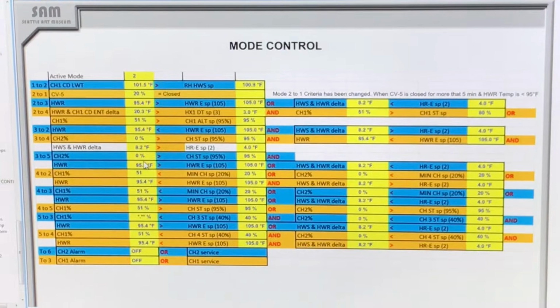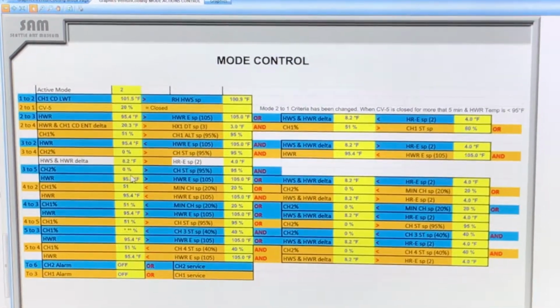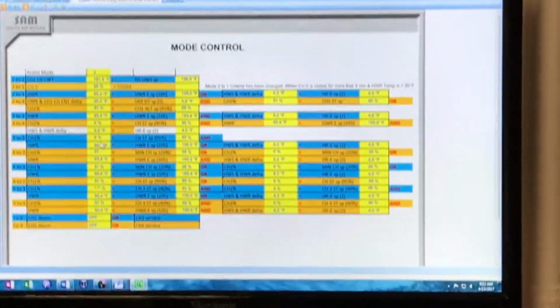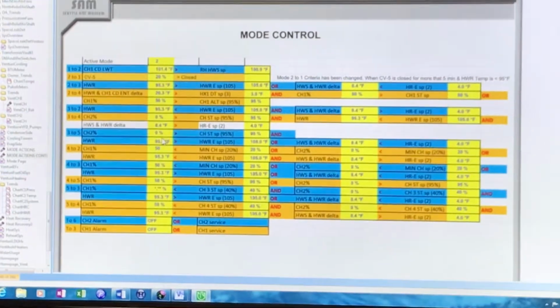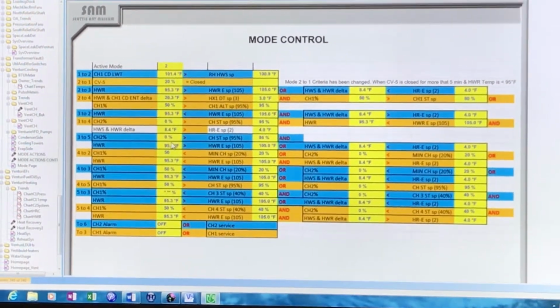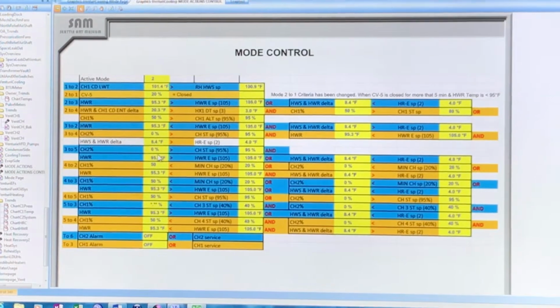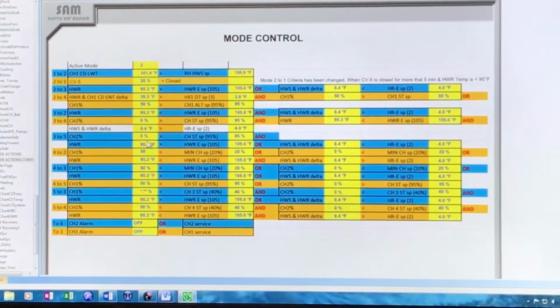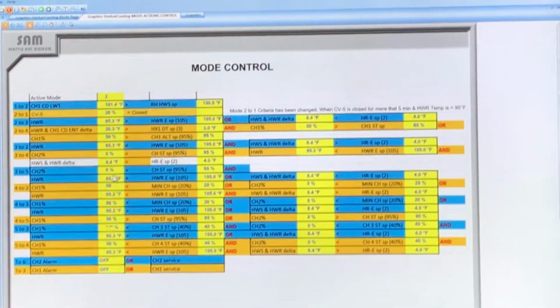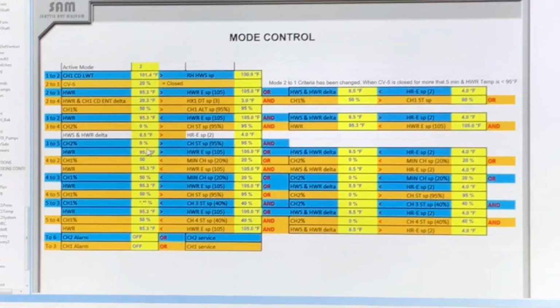No, you cannot override to 6. The computer will pick 6, right? We can't do the override to 6. No. We can override to 5. I know why he's saying this: we had that scenario a few weeks ago where chiller 2 failed and it never went into mode 6. I believe we addressed that. Yes. And on that table there is a bracket value, which is a default value. Normally you should always try to go back to that default value. And I think that's the basis.